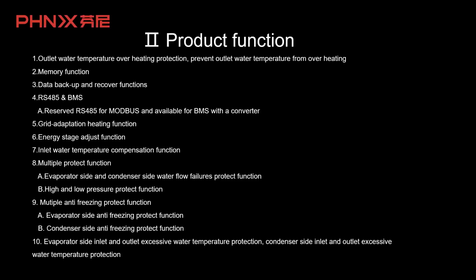Number 5, grid adaptation heating function. Number 6, energy stage adjust function. So what kind of function is the energy stage adjust function in the HeatMax water source heat pump unit? Do you have any ideas about energy stage? I don't think so. So let me ask you a question. How many compressors are in the big model? As far as I can remember, the biggest one, more than 100 kilowatts, has 4 compressors. So 4 compressors means 100% heating capacity output. What if 3 compressors are working? One compressor off. So what percentage of capacity is output? 75. Yes, exactly.